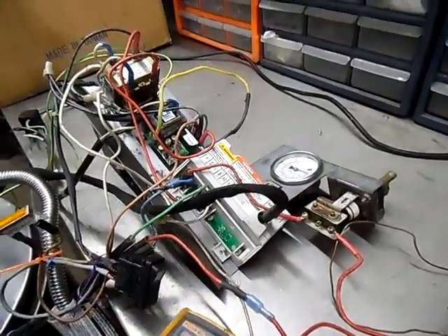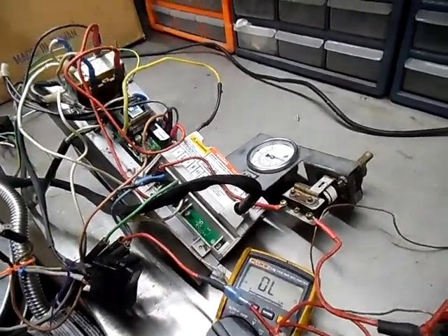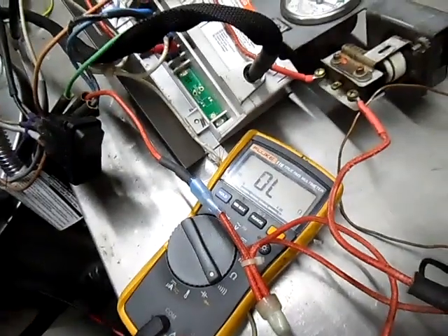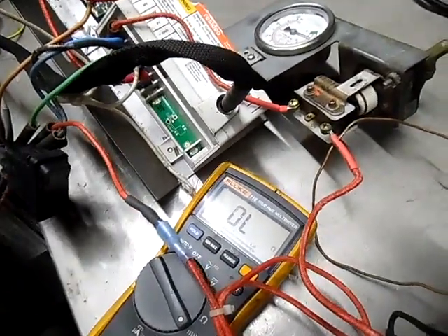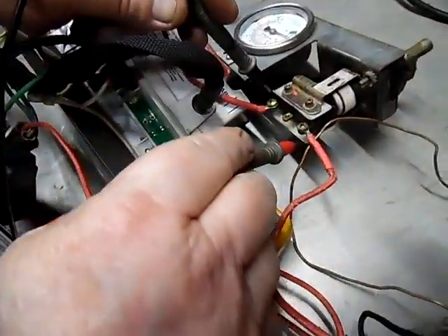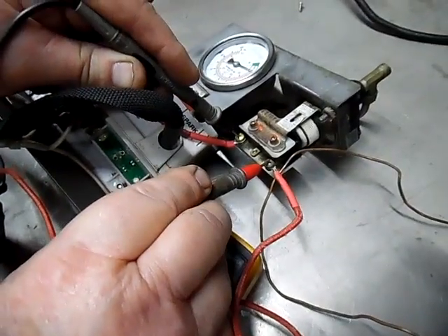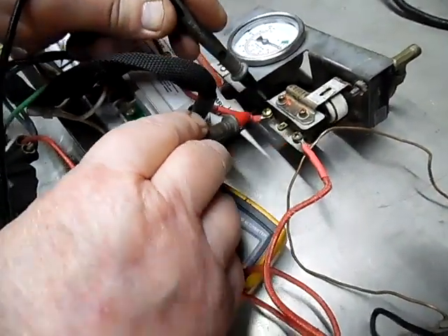Like I was saying, you put your meter on continuity. I do not have it plugged in. No power to the machine. You see here, I'm just checking the fuse. Same way I can check from one location to the next, across here on the pressure switch. See how it's on all the time? That goes to here, over to here.